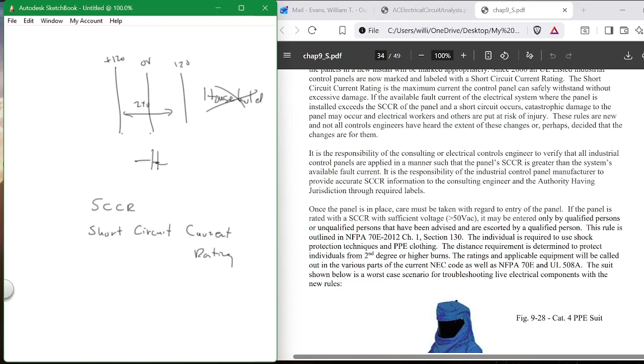When you walk up to a panel, if it doesn't have a tag that says SCCR (short circuit current rating), you're not supposed to open it. That puts you in a dilemma if someone tells you to open that panel anyway. You can remind them it should have an SCCR tag. If it doesn't, I'm not going to tell you to open it, because they haven't followed the law, which now requires this tag on every panel. So what happens if you don't have it? I don't know.